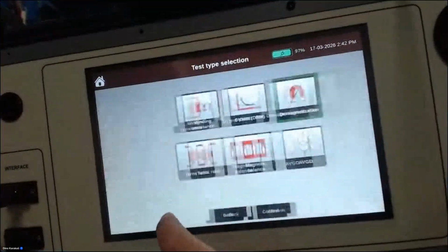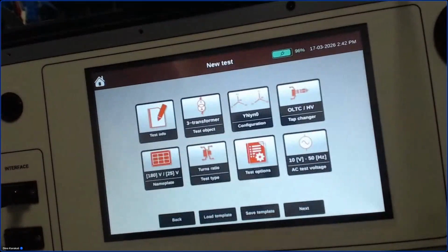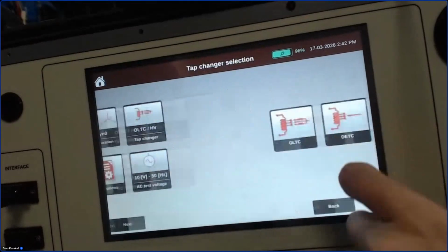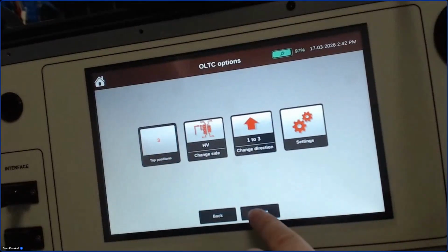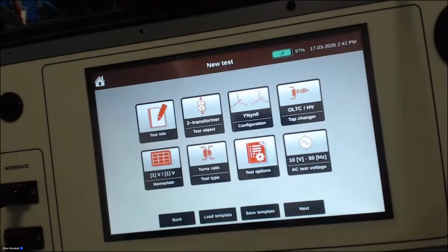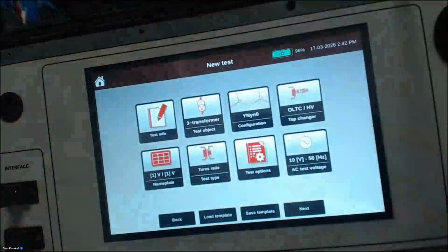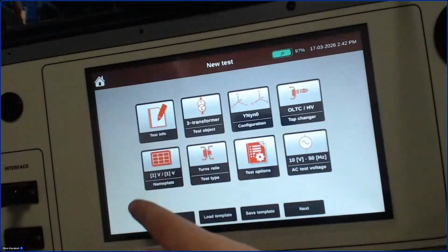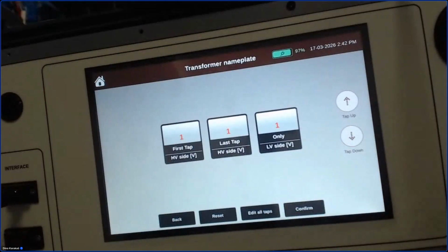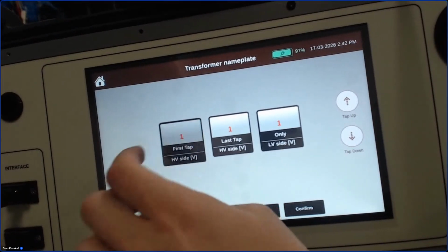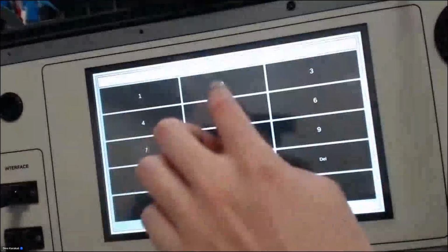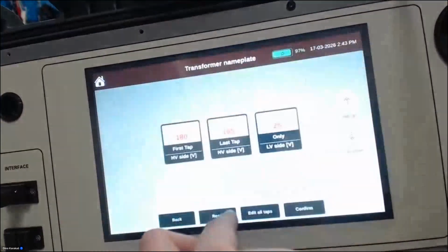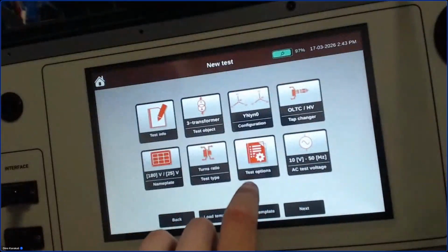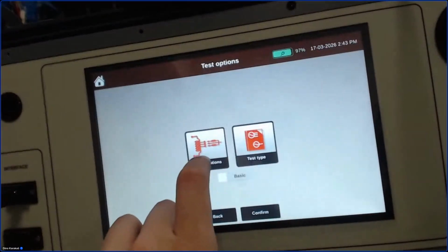We will select test type, turn ratio, confirm it. Again, we will go with 3 tap positions, the same. We can change this tap position on the nameplate. We will go down to position number 1. We press twice. We need to insert the nameplate values. Okay, turn ratio test. We have our configuration, test options.